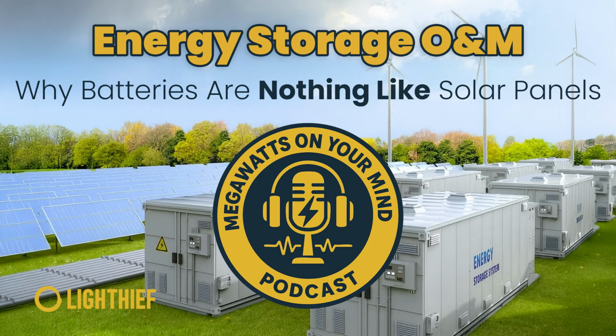The second type is flow batteries, fundamentally different technology. Energy is stored in liquid electrolytes in large tanks. To generate power, electrolytes are pumped through a cell stack, where electrochemical reaction occurs. The biggest advantage: power and capacity are completely independent. Power depends on stack size, capacity on tank size. This makes them ideal for long-duration applications, storing energy for many hours or days.